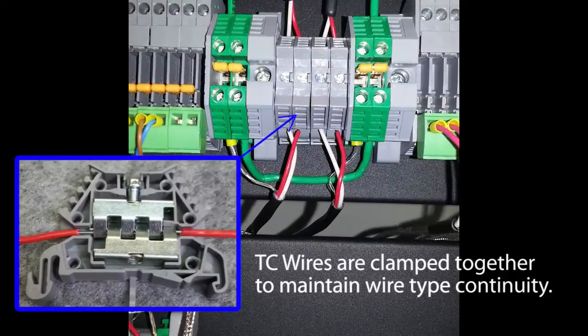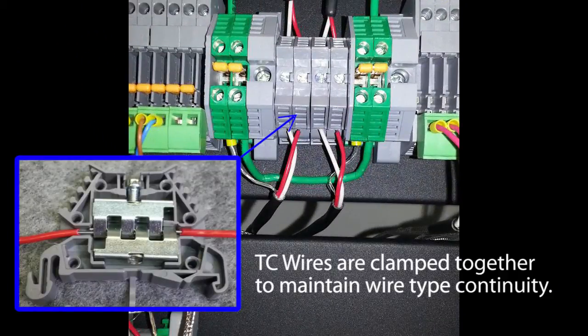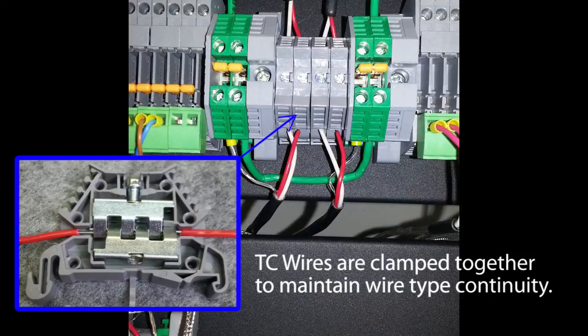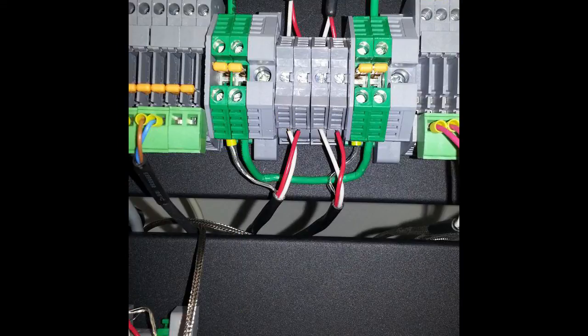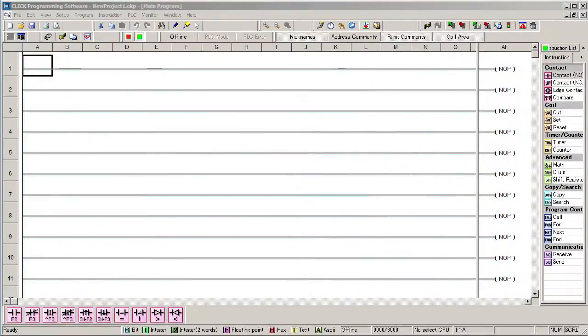And the thermocouples use the special thermocouple DIN rail terminal blocks. These ensure continuity of the special thermocouple wire by clamping the wires together instead of contacting them through a terminal block which would create unwanted thermocouple junctions. Well, that's it for the hardware, let's look at the software.